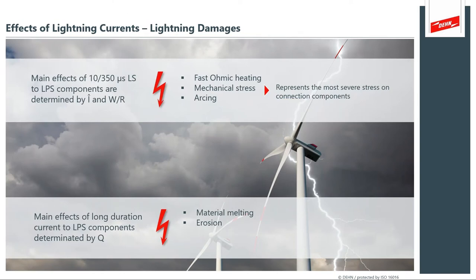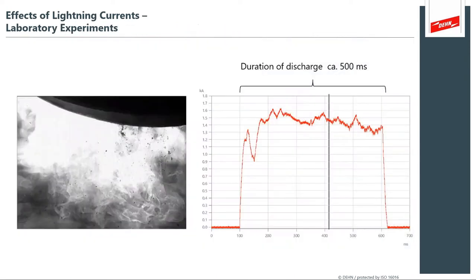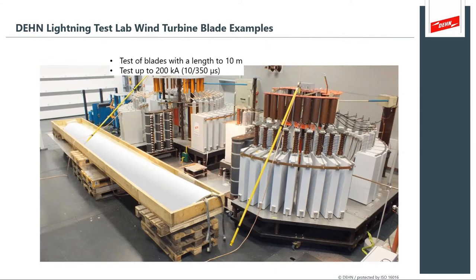Lightning has several causes and effects. The main effect from the long 10 by 350 peak magnitude stroke is a peak current, driving ohmic heating, mechanical stressing, and arcing. But long-duration events carry a tremendous amount of charge, causing material melting and erosion — for instance, on ball bearings and other load-bearing members of a turbine. In the laboratory, we're able to show the actual event and the actual types of damage expected from these lower-magnitude, longer-duration events. We've done a tremendous amount of research in our DEHN headquarters in Germany, engaging with manufacturers of wind turbine structures.